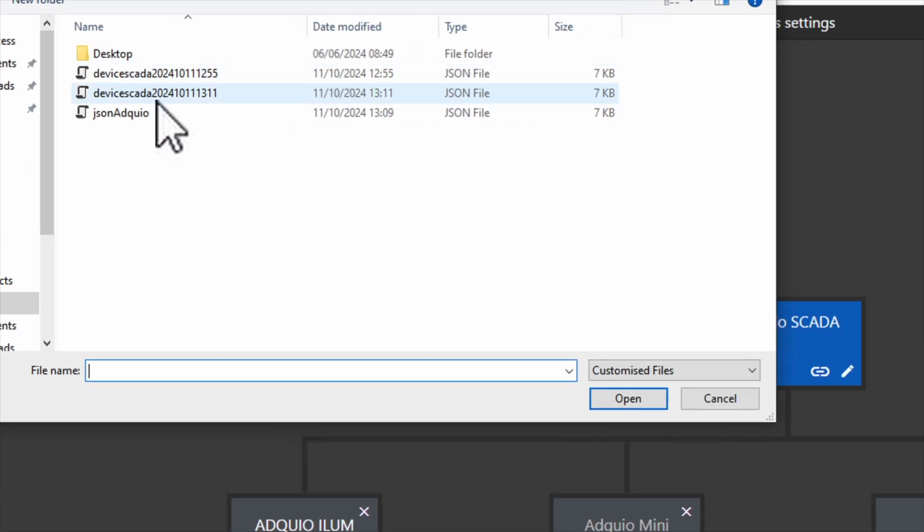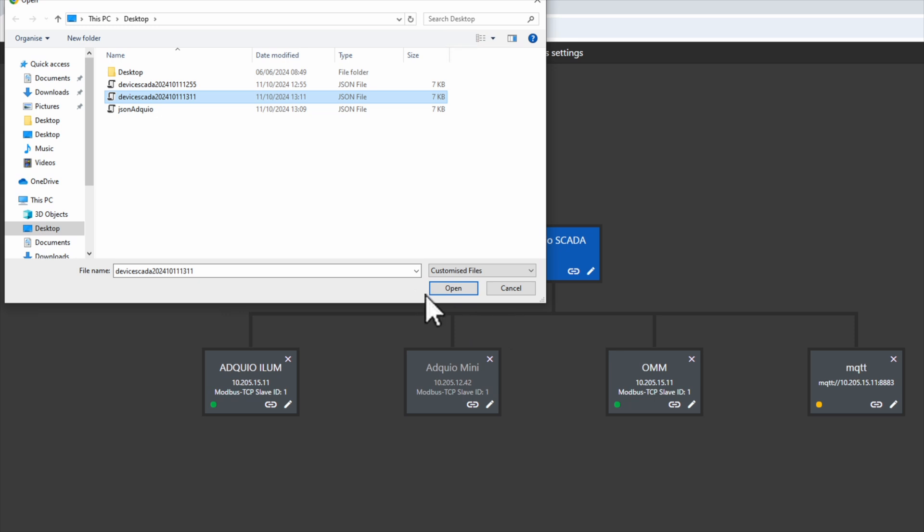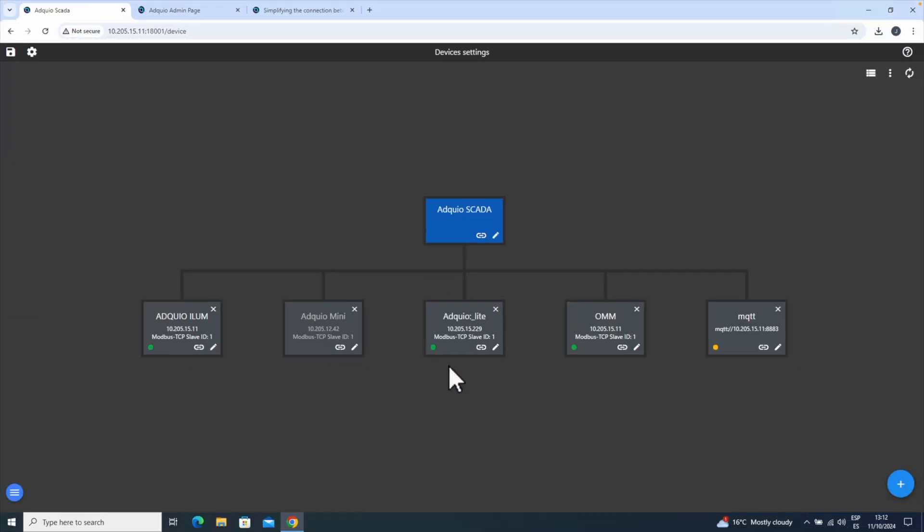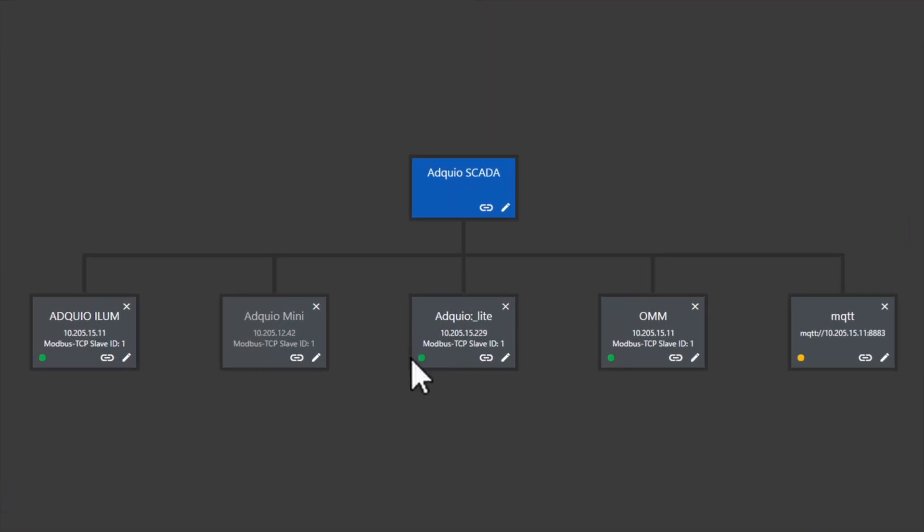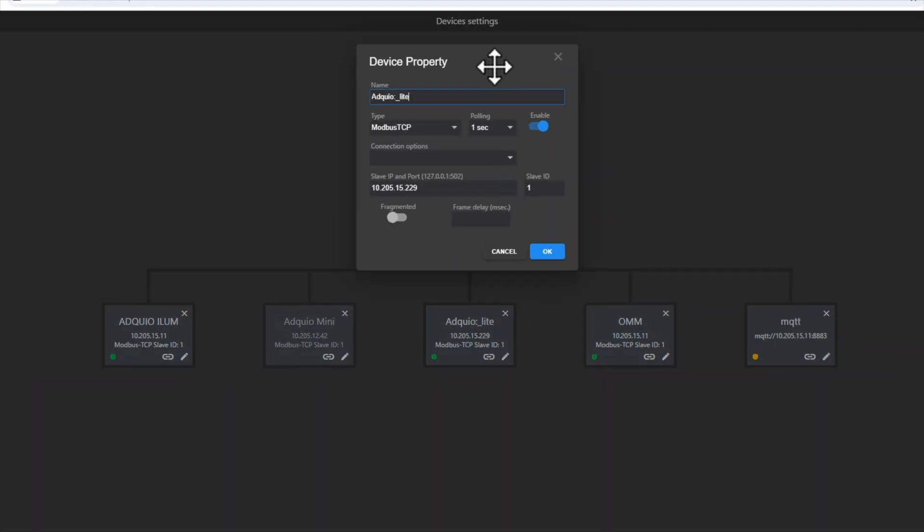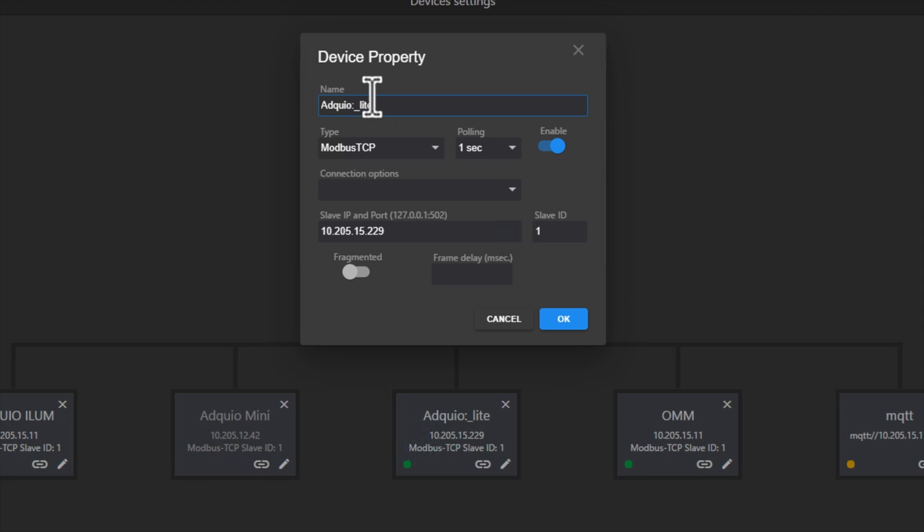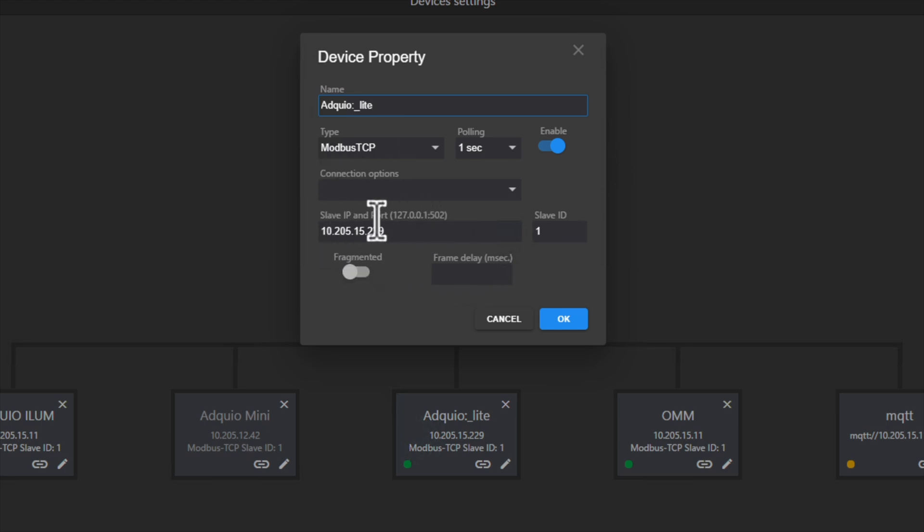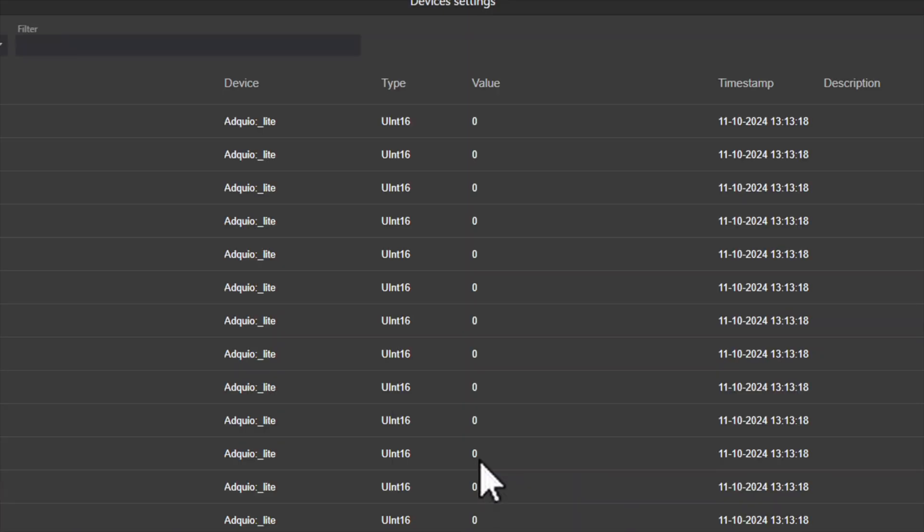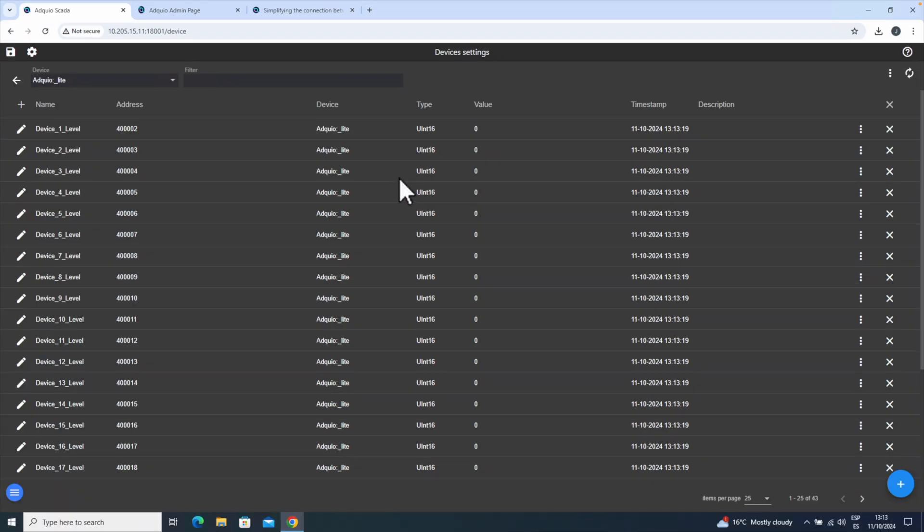We click the three dots, Import Devices, select the generated file, and we will see that our Adquio Lite is automatically recognized. The green dot indicates it is correctly connected. Let's take a look at how it looks. We can see that the name we gave it is already here, and it has been configured to use Modbus TCP with the IP address of our Adquio to collect the information.